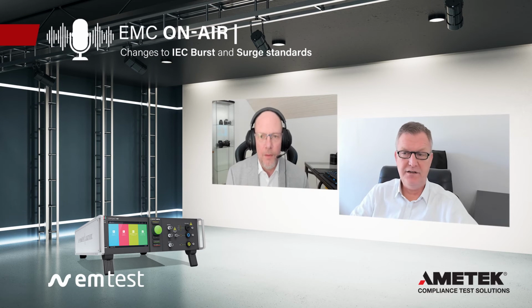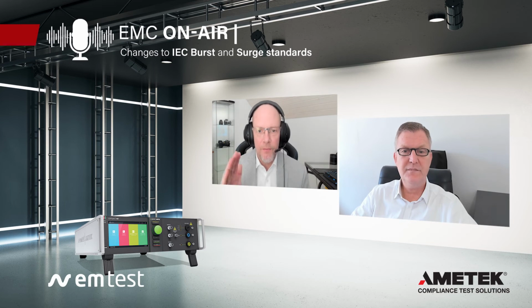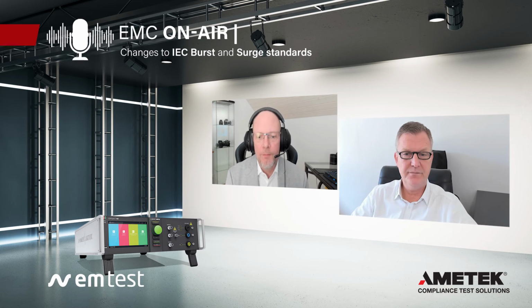Okay, and so go ahead. It's up to you. You can select whether you would prefer 5 or 100 kilohertz. You should use 100, and it could happen that a product standard specifies that you should use 5. So both combinations are specified in the new standard. Understood. So it's really the product standard that would tell you definitively if you have to do 5 kilohertz or 100 kilohertz. Interesting. Correct, yeah. Okay. Did we miss anything on burst?